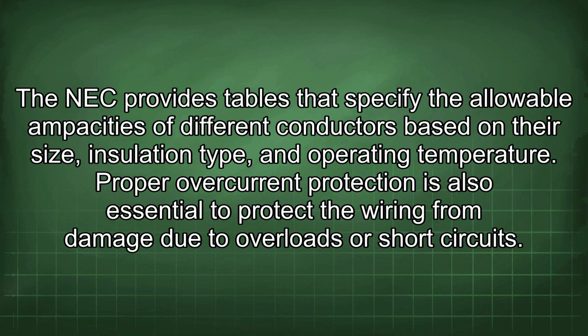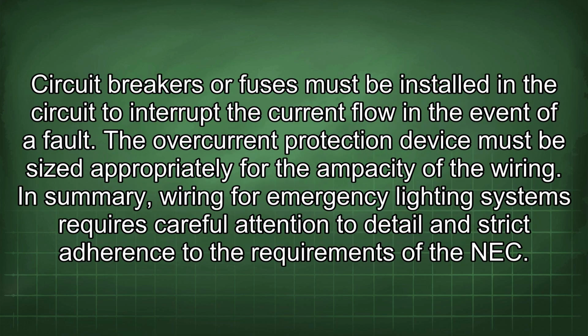Proper overcurrent protection is also essential to protect the wiring from damage due to overloads or short circuits. Circuit breakers or fuses must be installed in the circuit to interrupt the current flow in the event of a fault. The overcurrent protection device must be sized appropriately for the ampacity of the wiring.